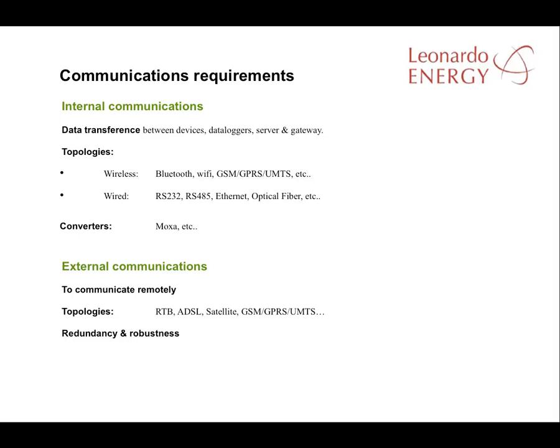When considering solar plant communications, we have to consider two types: internal and external. Internal communications are between devices, data loggers, and elements within the PV facility, while external communications are between our main office and the outside world. For internal communications, we have to decide between wireless and wired topologies; wired systems are recommended. The most commonly used are RS-485 and Ethernet systems. Converters can be used to change one signal to another. It is typical to use optical fibre running from the control room to the different areas across the site, and then to use a converter to get the data gathered from the RS-485 bus and convert it into an optical fibre bus.